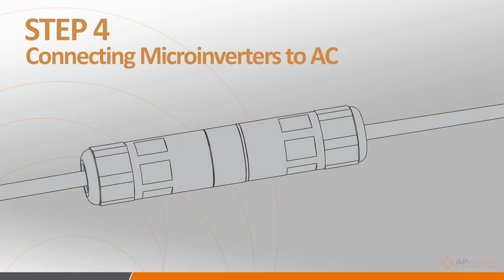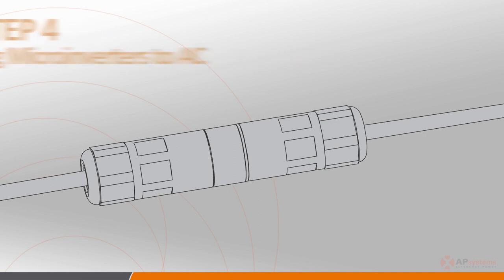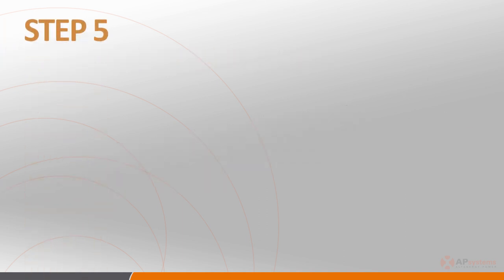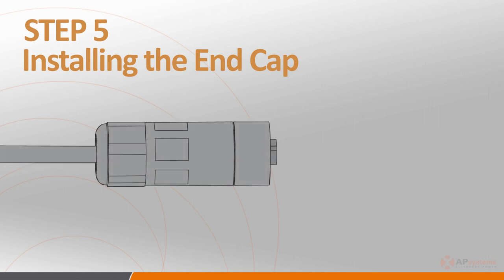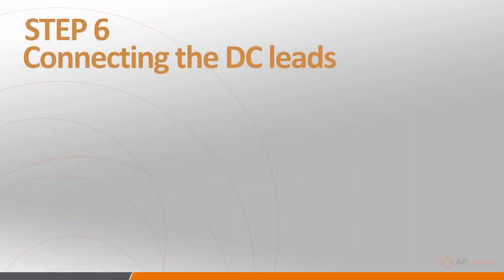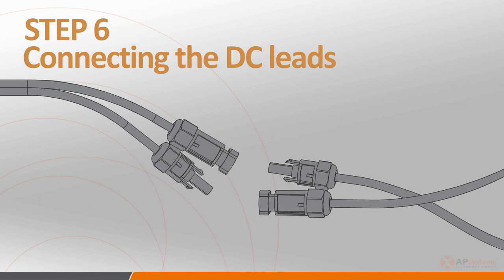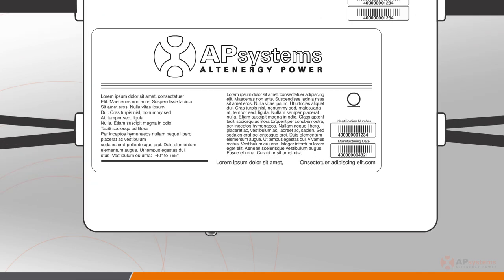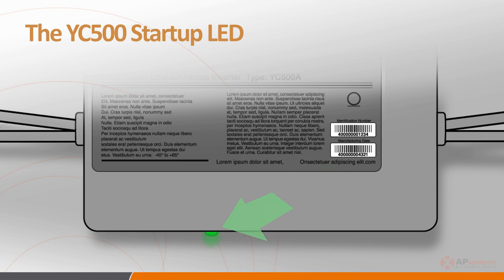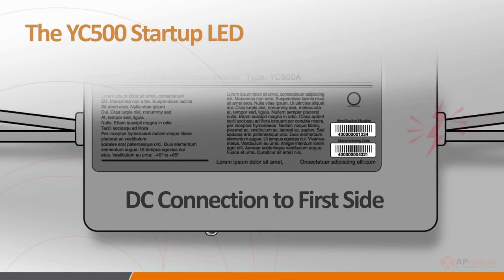Also, a word of caution when making these connections: do not string the AC cabling so tight that it is placing a stress on the connection points. Once the AC connections have been made, you're ready to move on to step 5 — installing the protective end cap onto the open AC connector on the last inverter in each branch circuit. Step 6: place the PV modules on the racking system and connect the DC leads from each of the PV panels to the microinverters, making sure that the connectors are securely snapped into place. The LED on the microinverter will flash green three times when DC power is first applied, indicating a successful connection.